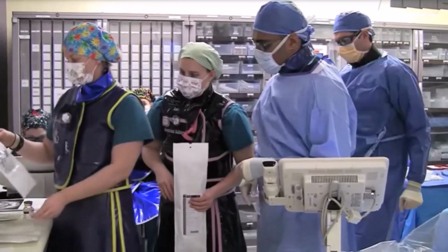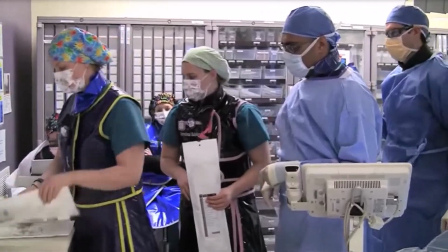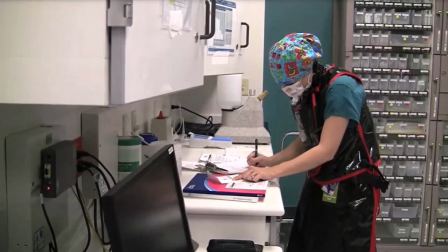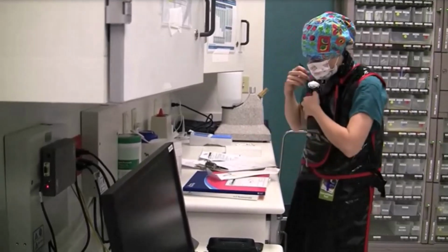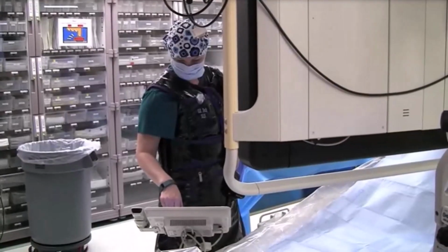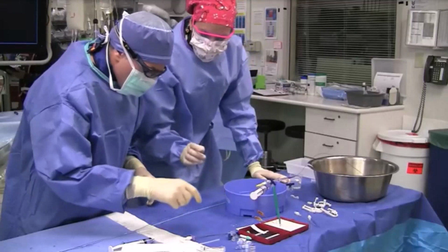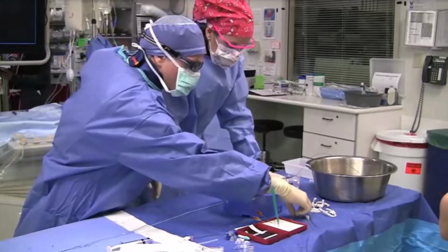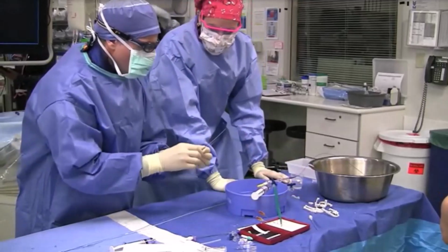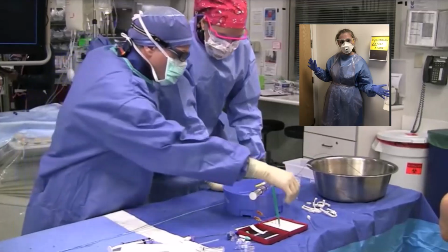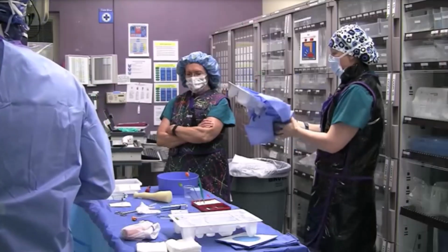When performing fluoroscopy procedures, it is crucial to follow specific guidelines to ensure the safety of medical staff. Here are some key recommendations. Lead aprons. Wear a lead apron that provides at least 0.25 mm lead equivalents on the back and with overlapping 0.25 mm on the front, totaling 0.5 mm, to protect against scatter radiation.